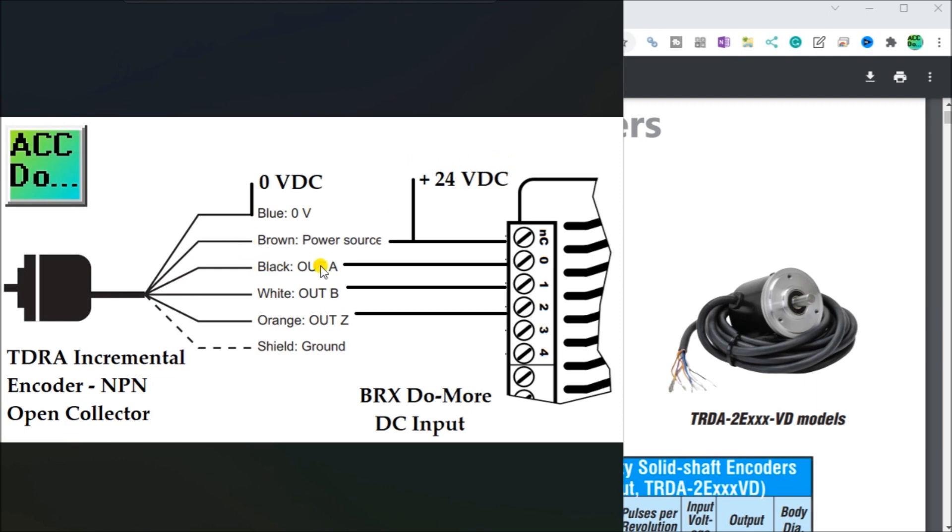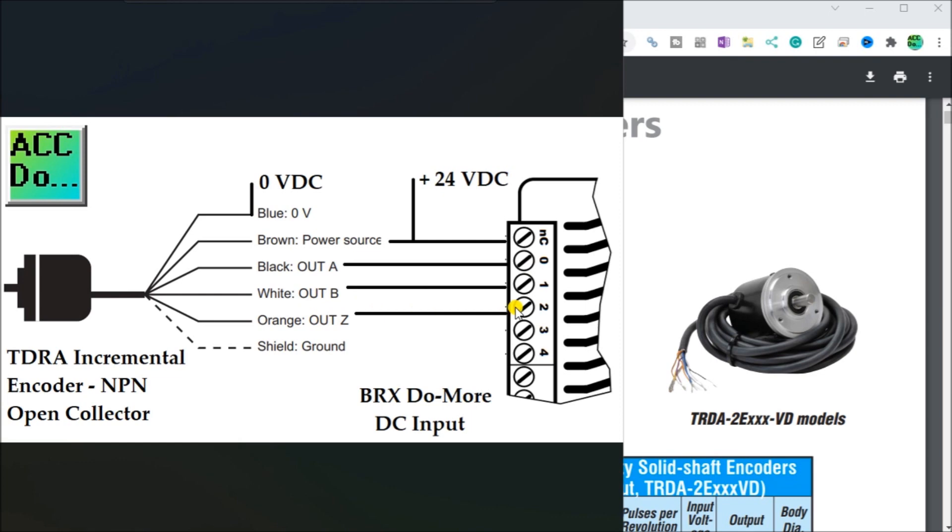Because we have an NPN sinking output of our encoder, we'll have a sourcing input of our PLC. We have our phase A, our black wire, going into X0. X1 is our output B, which is our white wire of our encoder. And our orange wire is output Z, which is what we'll be using in our program, which is X2. That is our wiring of our incremental encoder to our BRX controller.